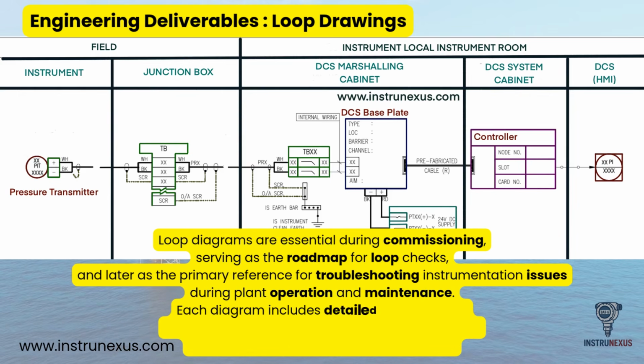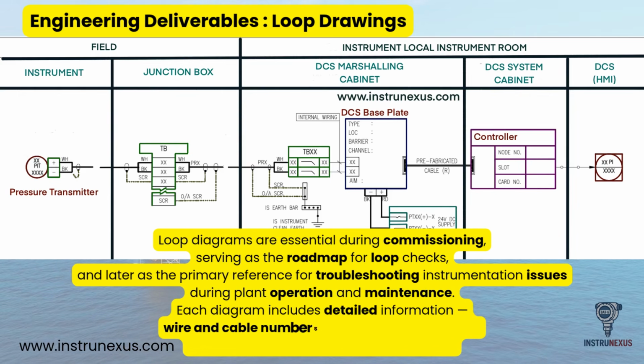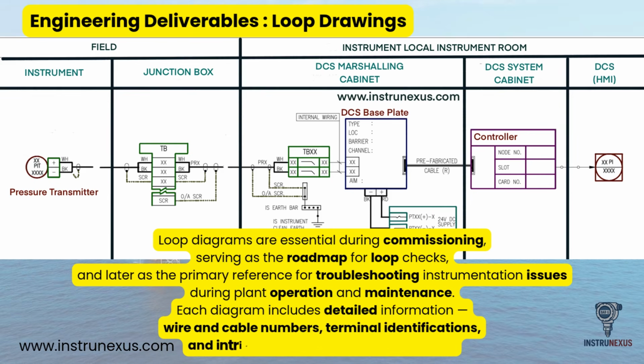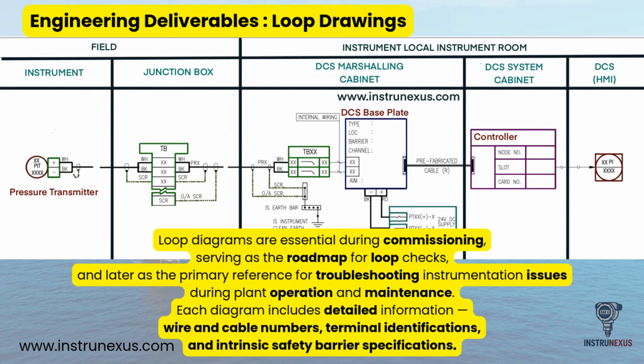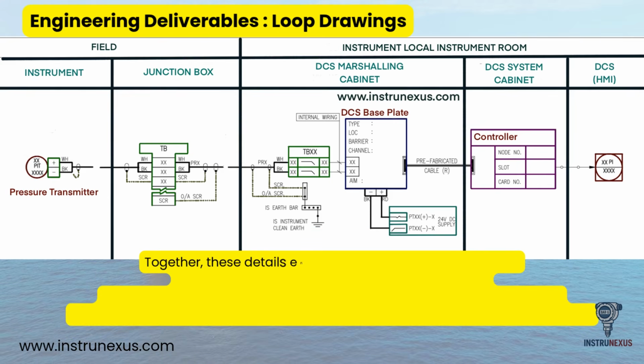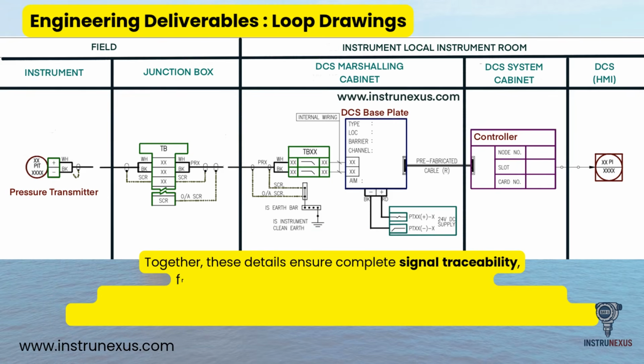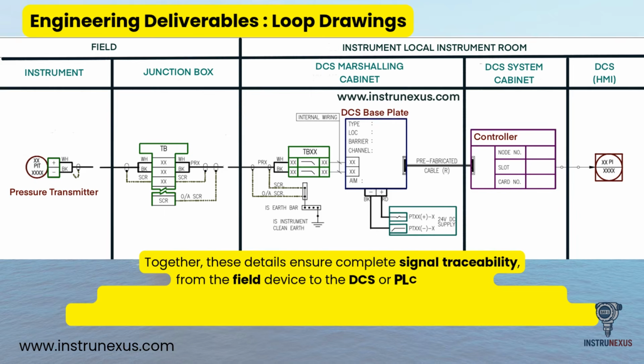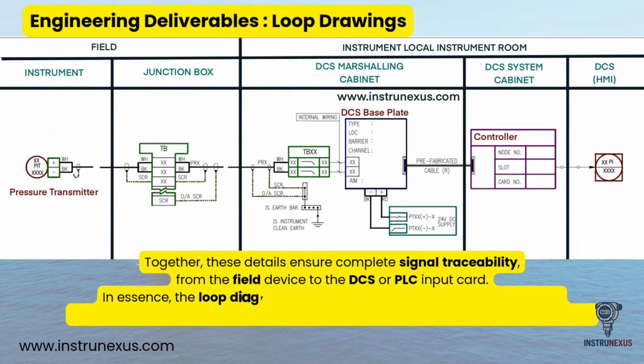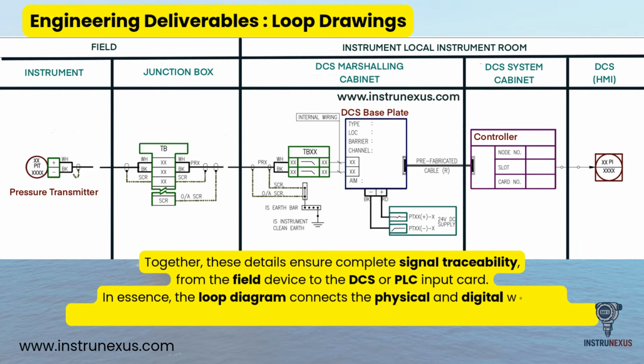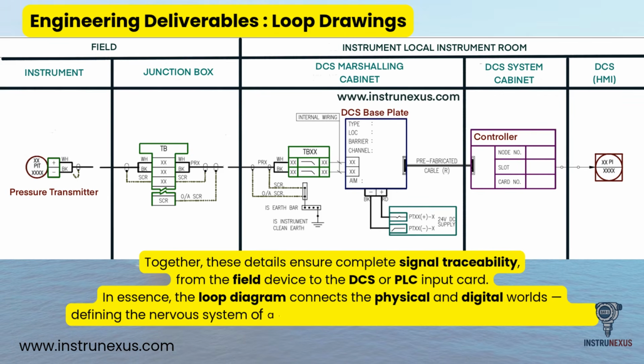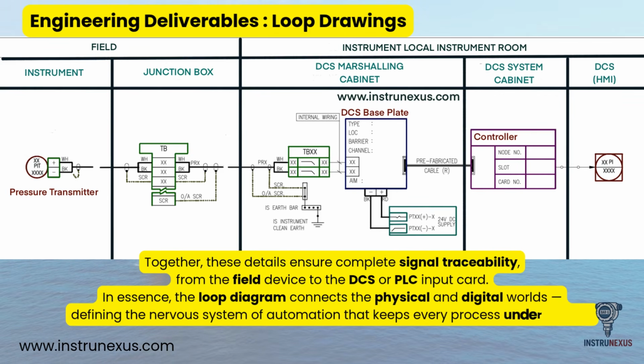Each diagram includes detailed information: wire and cable numbers, terminal identifications, and intrinsic safety barrier specifications. Together, these details ensure complete signal traceability from the field device to the DCS or PLC input card. In essence, the loop diagram connects the physical and digital worlds, defining the nervous system of automation that keeps every process under control.